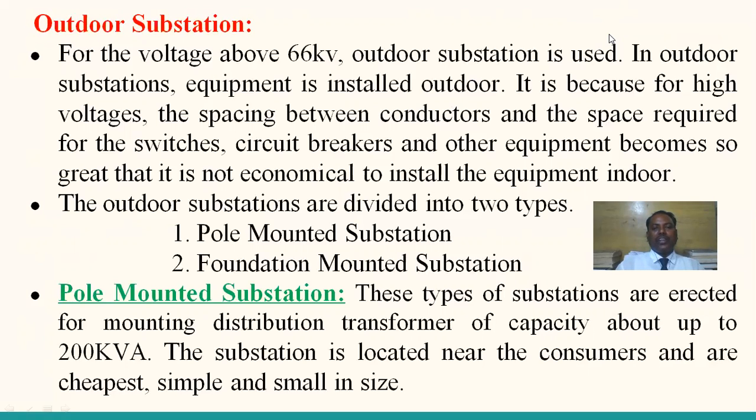The outdoor substation is very familiar. Almost all the students have awareness of the substation, and a substation is generally located outside the town or village. When high voltages and high loads are required, we go for outdoor substations. For voltage above 66 kV, an outdoor substation is used. In outdoor substations, all the equipment is installed outdoors, openly.